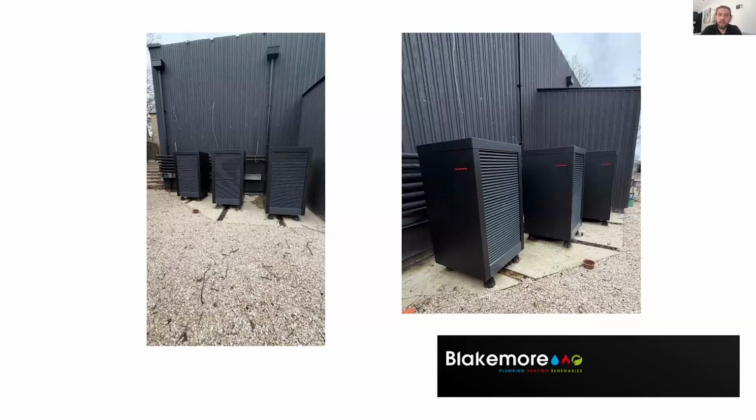We've run it from a full KNX system internally. Because the house is so vast and because we only wanted to load one cylinder at once, he's linked it to his own automation. So depending on what rooms they're in, we can pull and load the rooms. His MVHR comes on, and one cylinder he'll use. There's 5 secondary return pumps that are pulling to different points in the house, depending on which part of the house is calling. So it was quite challenging to be able to deliver all this.